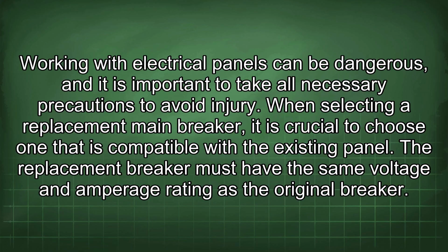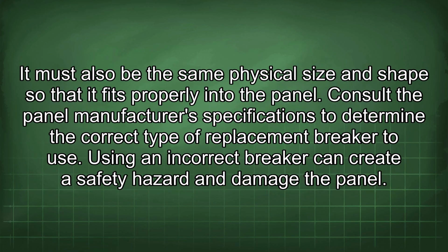When selecting a replacement main breaker, it is crucial to choose one that is compatible with the existing panel. The replacement breaker must have the same voltage and amperage rating as the original breaker. It must also be the same physical size and shape so that it fits properly into the panel. Consult the panel manufacturer's specifications to determine the correct type of replacement breaker to use. Using an incorrect breaker can create a safety hazard and damage the panel.